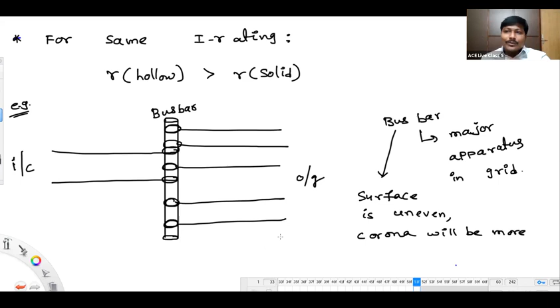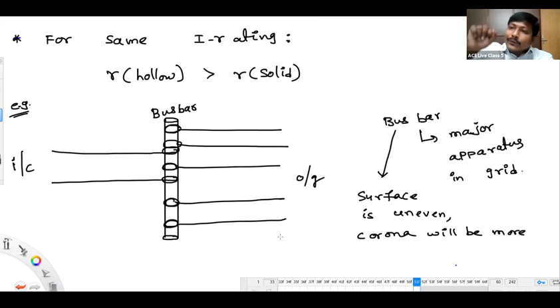Tell me, in view of corona, which conductor we have to select for the bus bar? That's the question. This is how you have to understand. Because of the number of interconnections, corona is more on the bus bar. So conductor selection is done in such a way that the conductor should offer less corona. If you select that way, we can expect the corona will be less in the bus bar, even though we have interconnections or an uneven surface. Have you understood this?